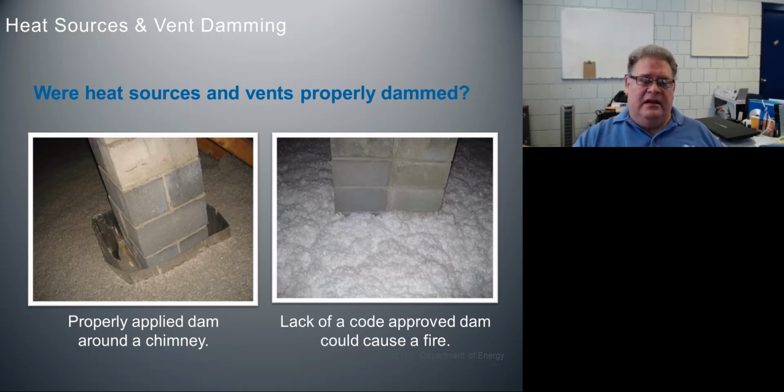dam. Now, one thing that I want to bring into this conversation is the dam is required because of NFPA 211. That's the National Fire Protection Association, their standard 211, which deals with solid or wood-fueled appliances, and that's what we think that this chimney is going to be falling under, a wood-fueled appliance. They're saying that you need 2 inches to combustibles.